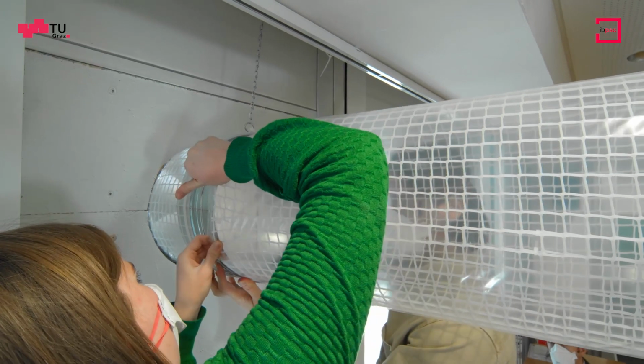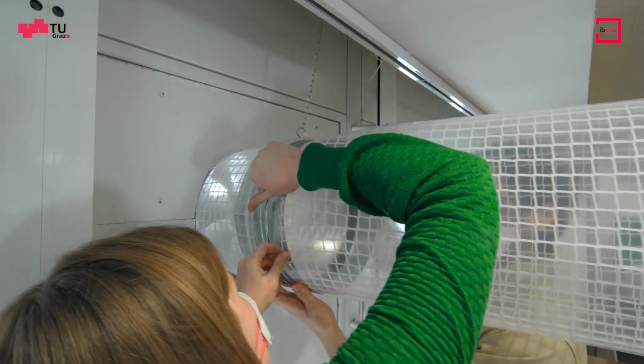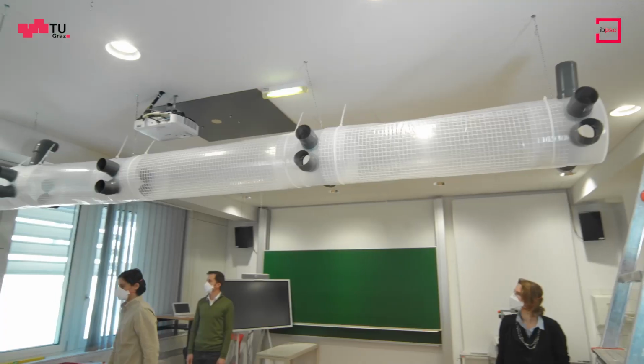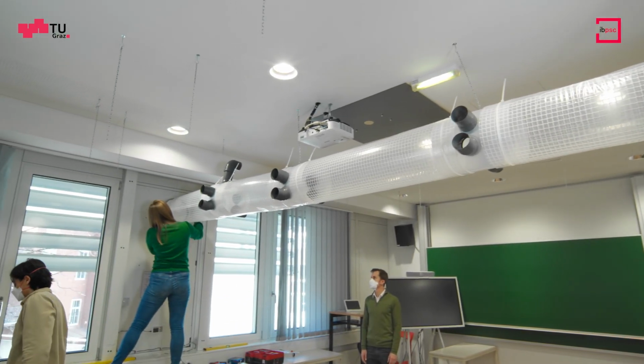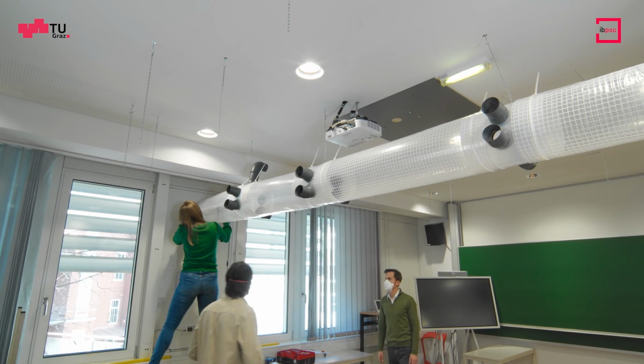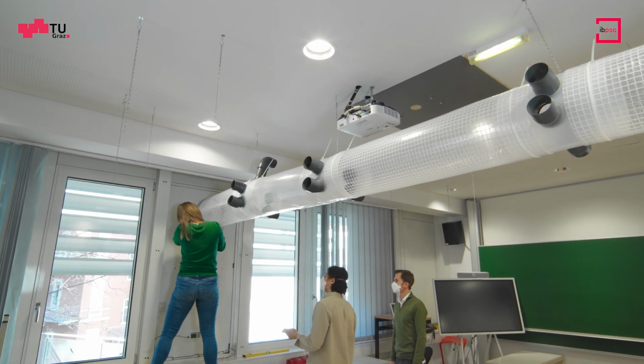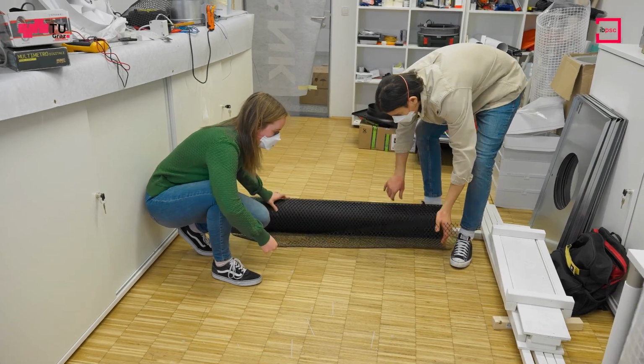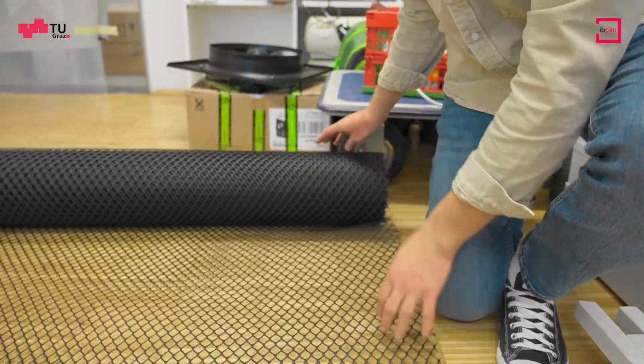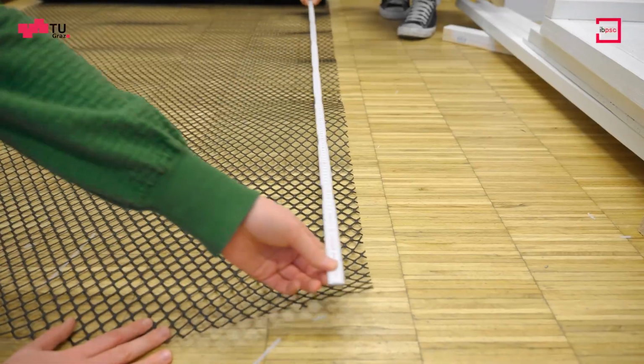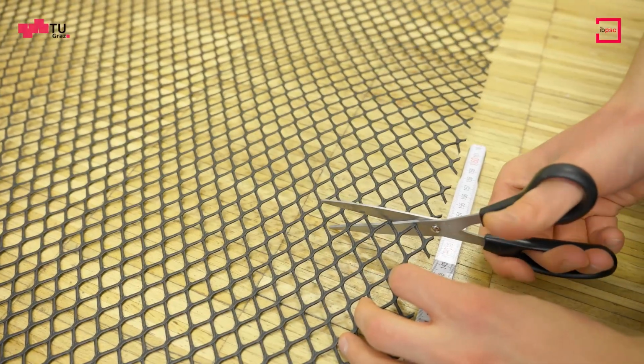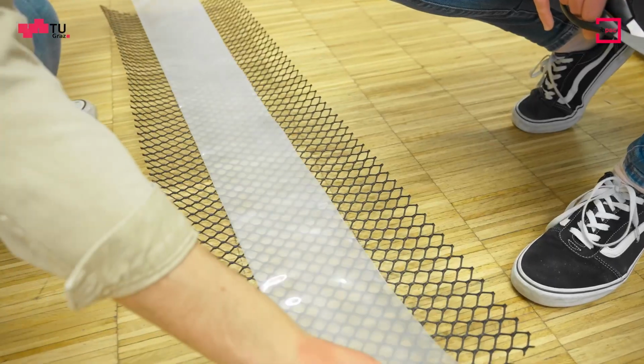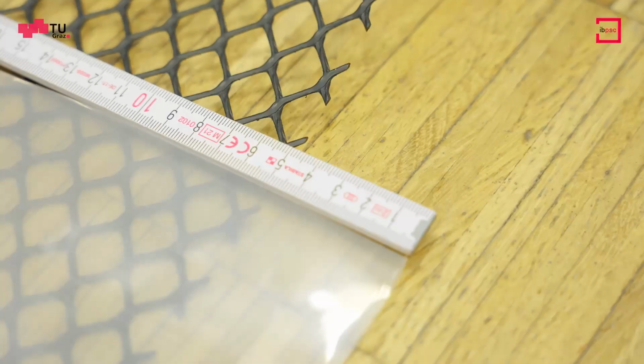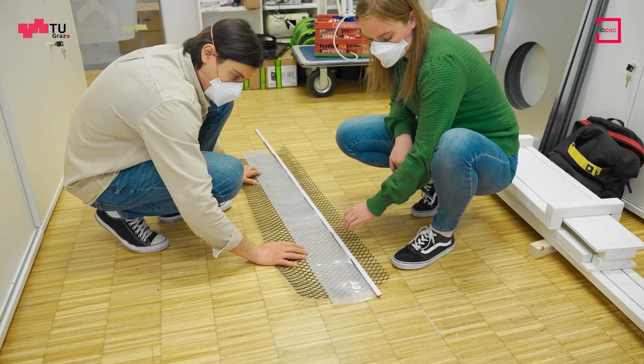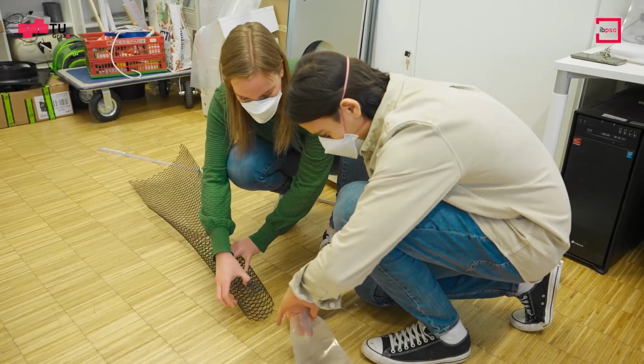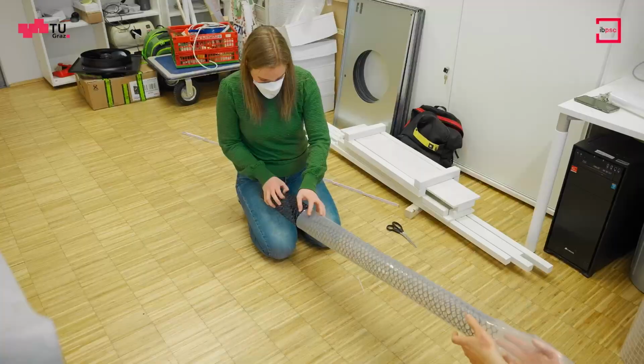Once the main duct is suspended and correctly aligned, it can be fixed to the fan. The system can be run like this, with stale air now being extracted from multiple points across the room. The branch ducts are pre-made in sections in the same way as the main duct, just with a 90mm diameter plastic sleeve. The outer sleeve should be about 5 centimeters longer than the inner mesh, allowing it to overlap the connection piece to which it is fixed.